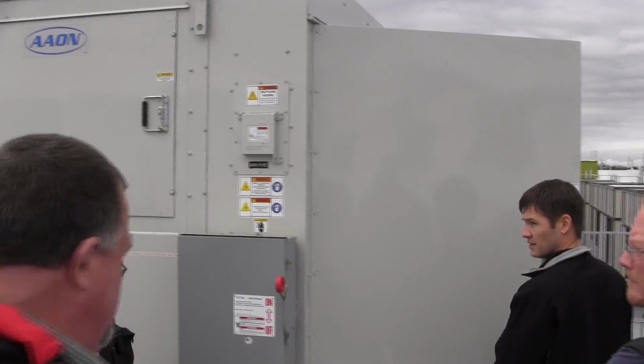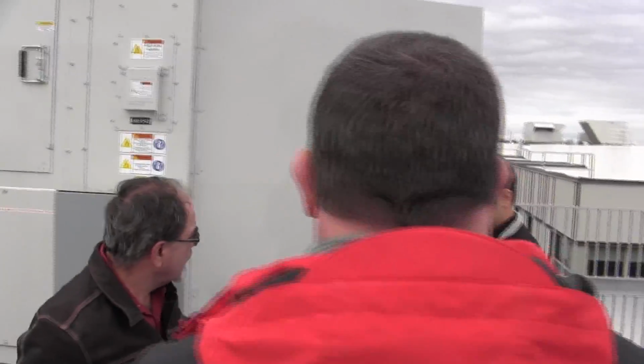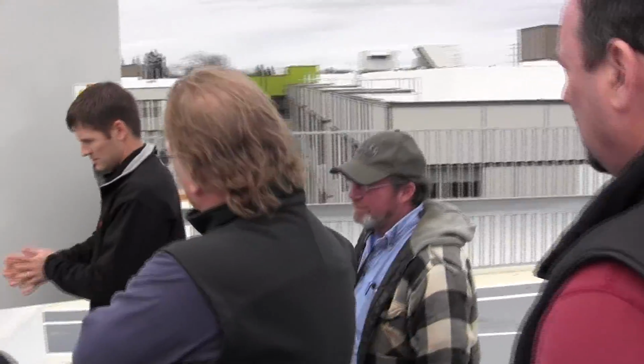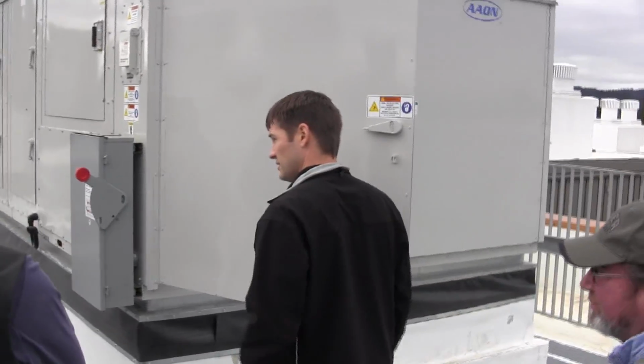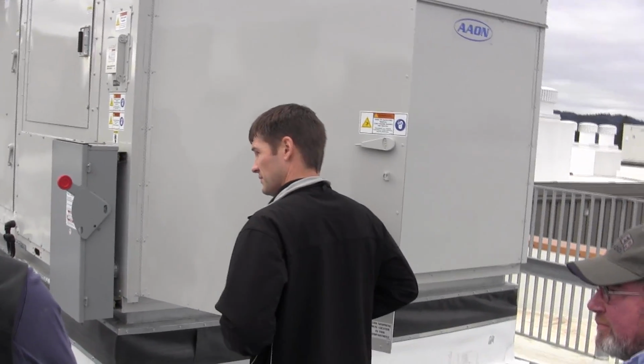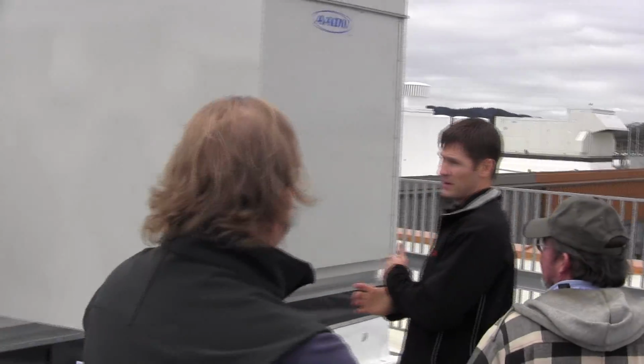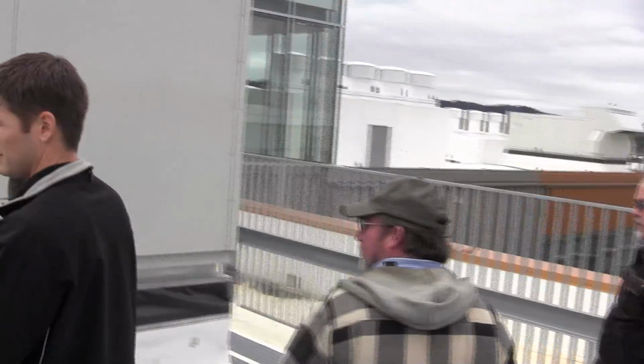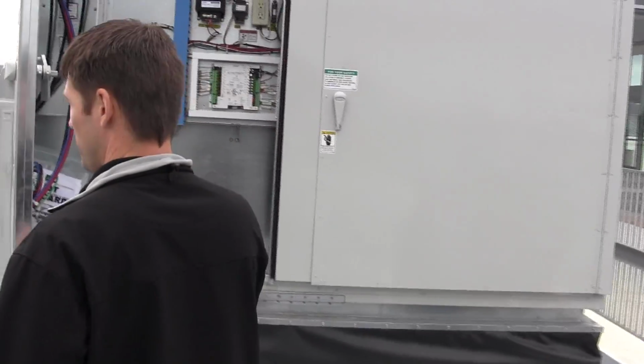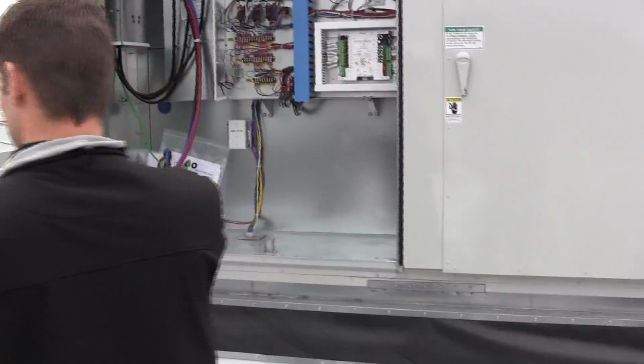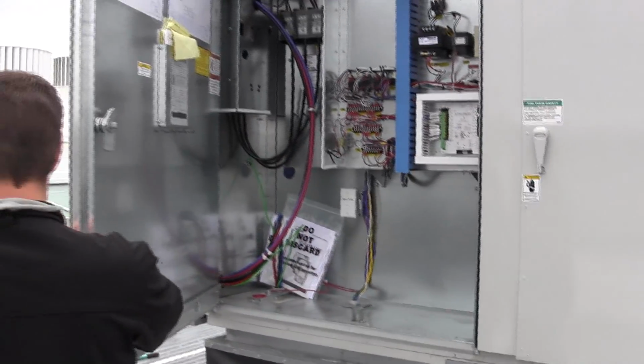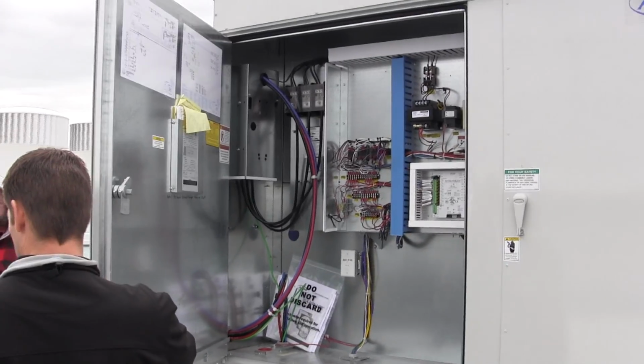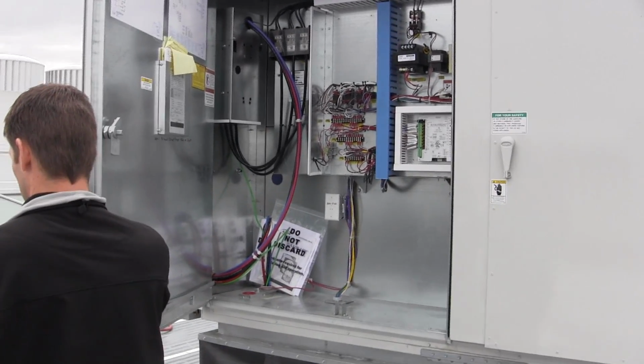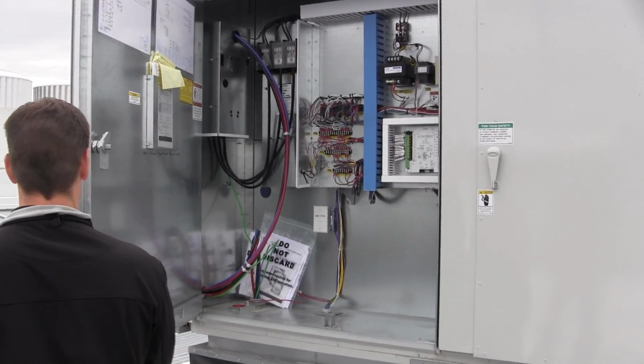Where is the lubrication on that fan? Probably on the bearing. Okay, lock it out, get in there. And there is a bearing on each side of the wheel. There's a bearing on the inlet and on the outlet. Sometimes on plenum fans it's just the bearing on the outlet and there's nothing on the intake, but there's one on each side.